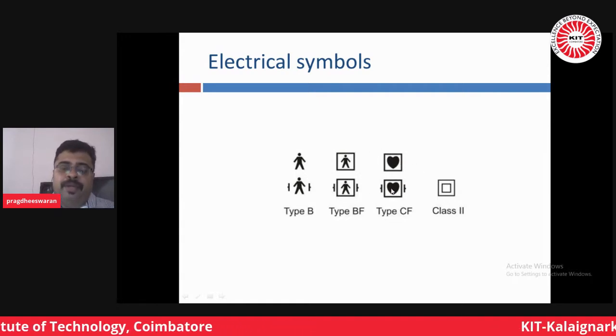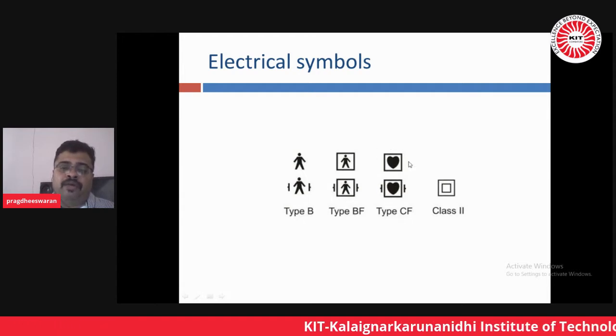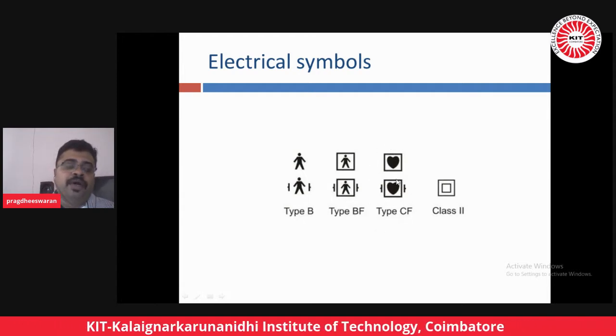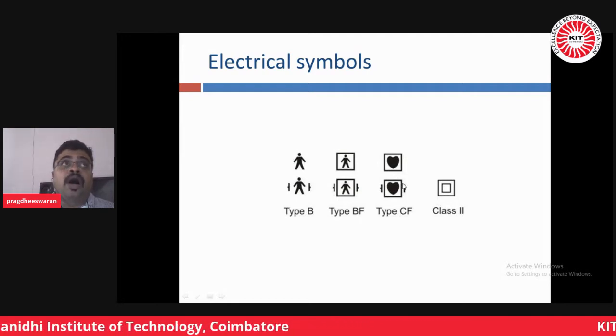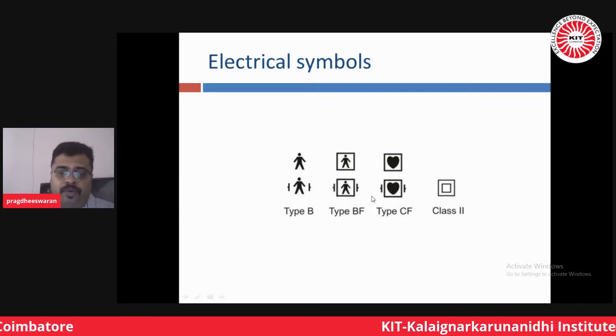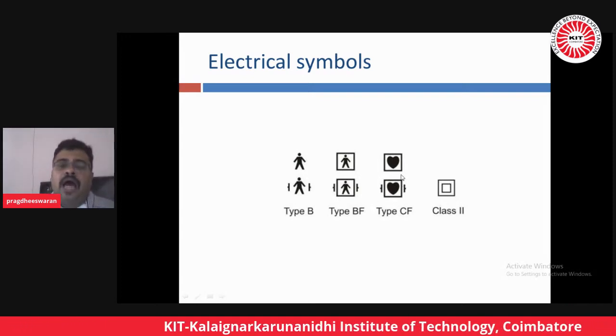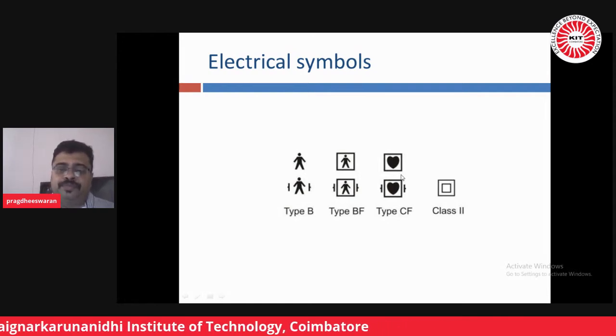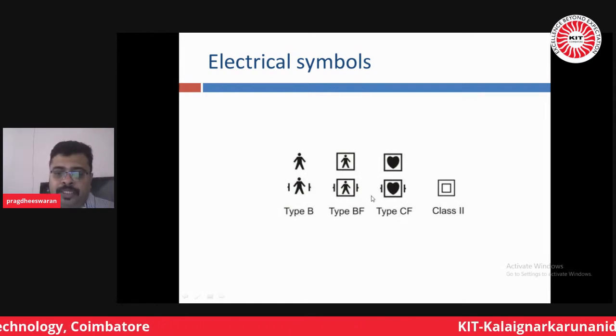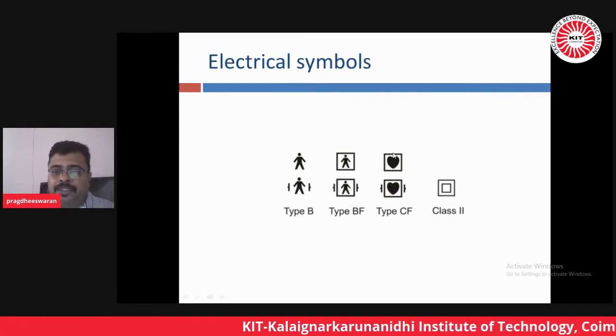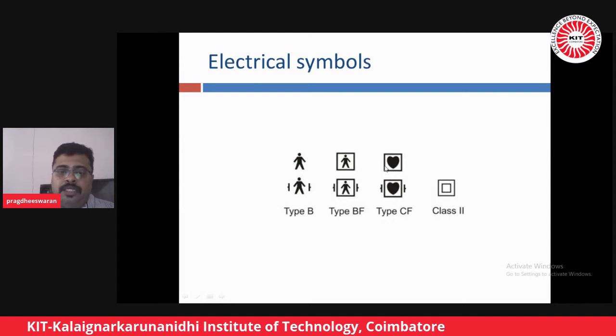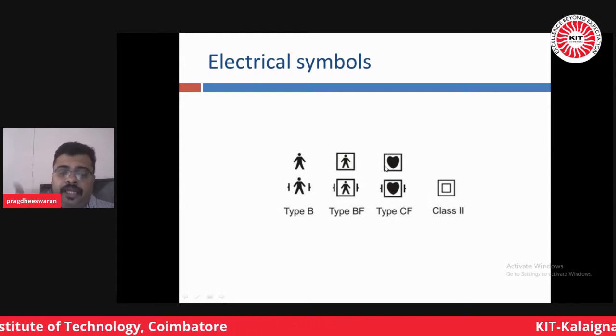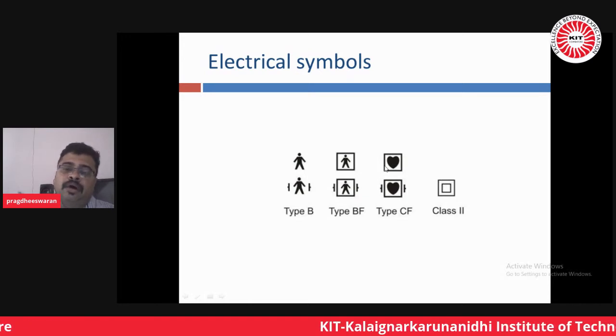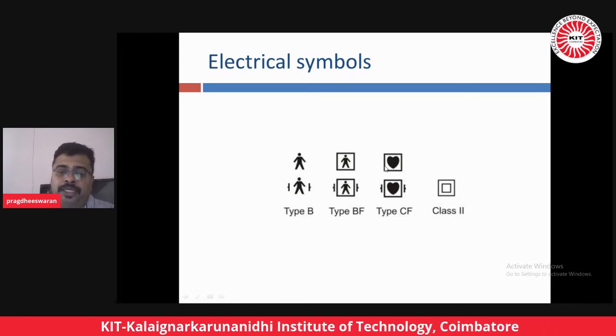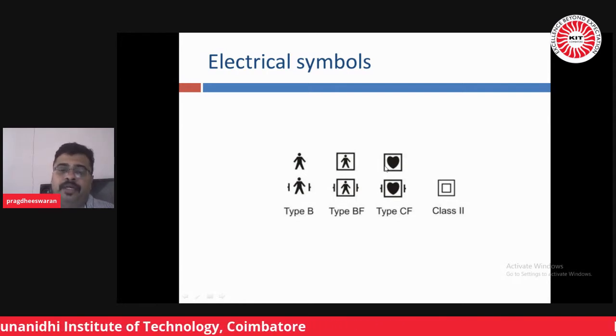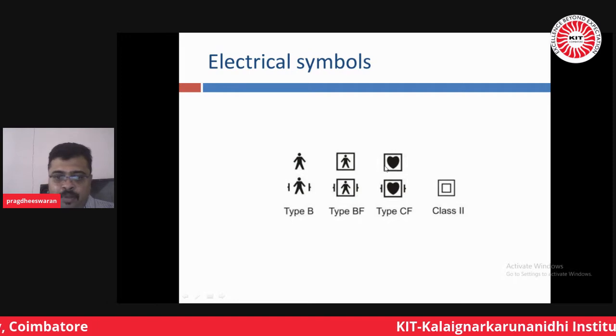equipment, like a defibrillator, an ECG machine and a pacemaker, comes with a CF type of symbol, which is called cardiac float. This has a very minimum allowable leakage current to the patient. You can see two types of cardiac float. One type is with just a heart in a box. This says that it has reinforced insulation. It operates on AC as well as DC, and it can also be applied with a defibrillator. So nothing will happen to the machine, and nothing will happen to the patient either.